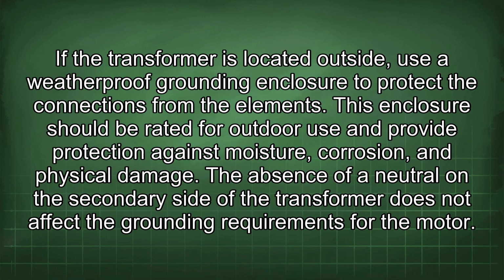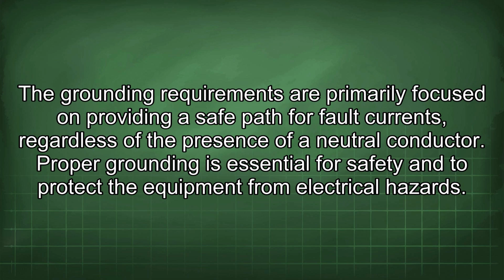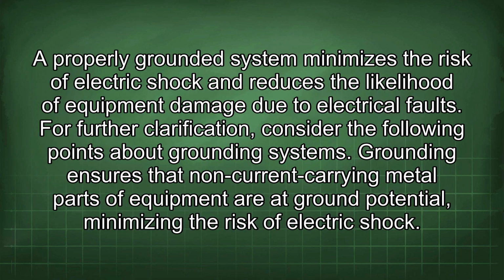If the transformer is located outside, use a weatherproof grounding enclosure to protect the connections from the elements. This enclosure should be rated for outdoor use and provide protection against moisture, corrosion, and physical damage. The absence of a neutral on the secondary side of the transformer does not affect the grounding requirements for the motor. The grounding requirements are primarily focused on providing a safe path for fault currents, regardless of the presence of a neutral conductor. Proper grounding is essential for safety and to protect the equipment from electrical hazards. A properly grounded system minimizes the risk of electric shock and reduces the likelihood of equipment damage due to electrical faults.